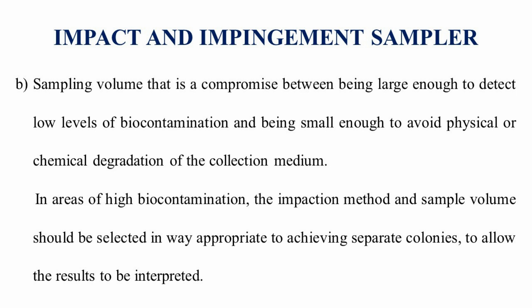The second characteristic of impact and impingement samplers is the sampling volume, which is a compromise between being large enough to detect low levels of biocontamination and being small enough to avoid physical or chemical degradation of the collection medium. If the chances of biocontamination are low, we have to sample a large amount of air. If the biocontamination level is high, we have to sample a minimum quantity.